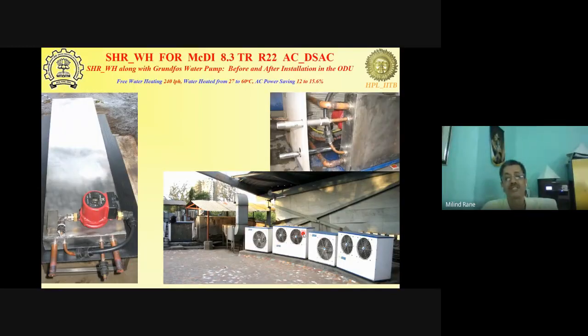Then this was the first McDonald's unit which we deployed, where the power saving on the AC was 12 to 15.6%. Of course, the AC cooling capacity might have also gone up, but we didn't have any reliable means of measuring it. And it was generating around 240 liters of hot water per hour, heating from 27 to 60 degrees centigrade in a single pass.